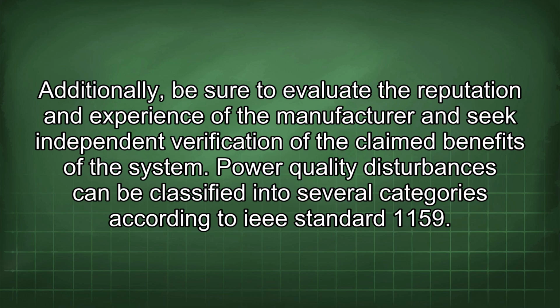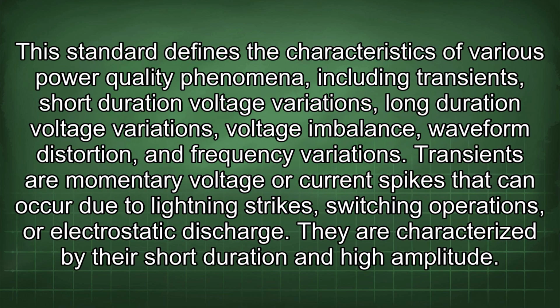Power quality disturbances can be classified into several categories according to IEEE Standard 1159. This standard defines the characteristics of various power quality phenomena, including transients, short-duration voltage variations, long-duration voltage variations, voltage imbalance, waveform distortion, and frequency variations. Transients are momentary voltage or current spikes that can occur due to lightning strikes, switching operations, or electrostatic discharge. They are characterized by their short duration and high amplitude.